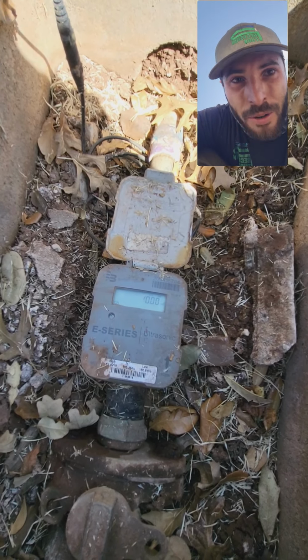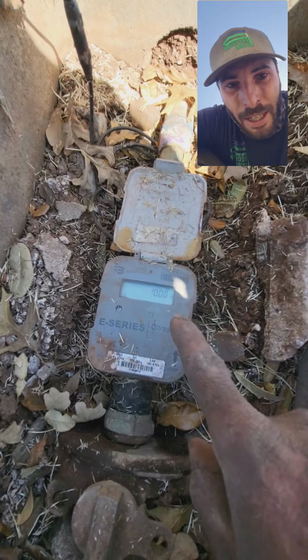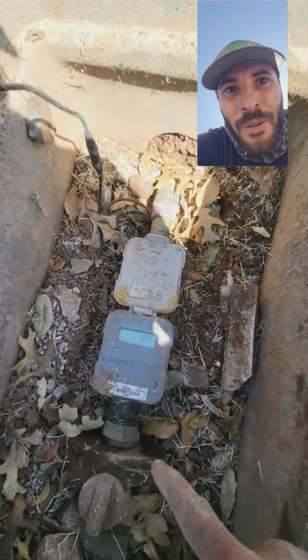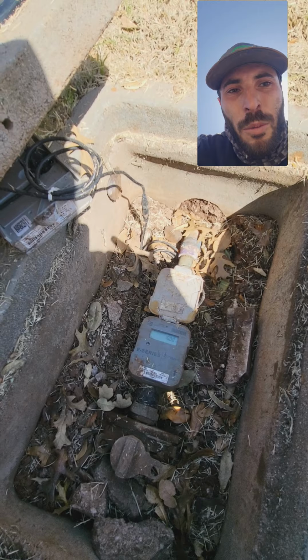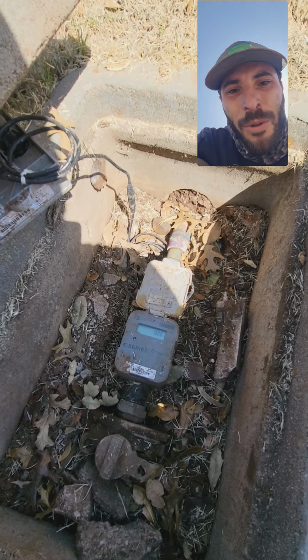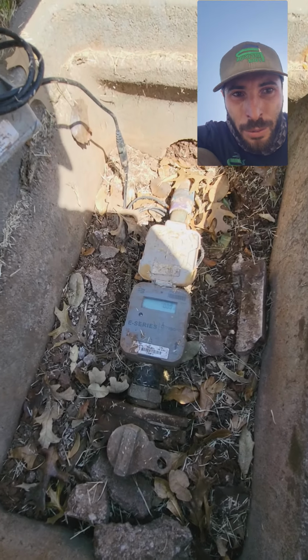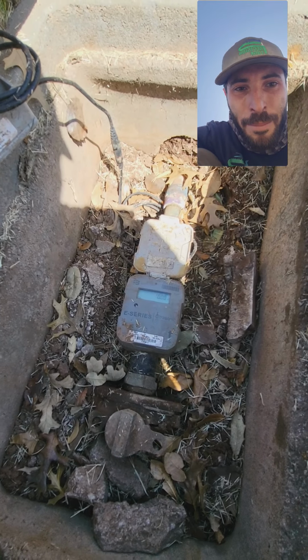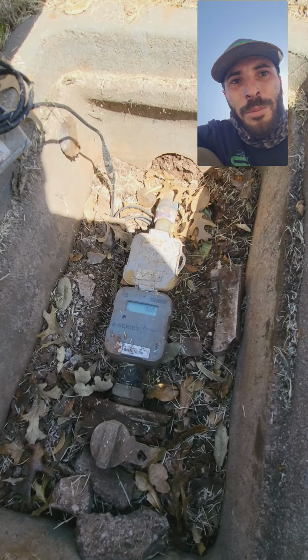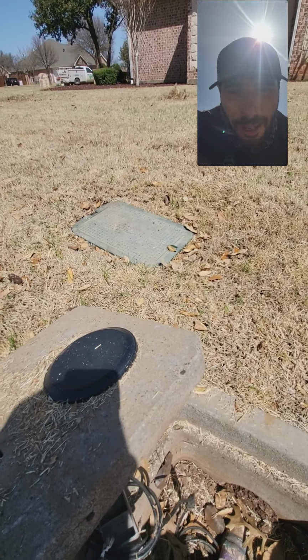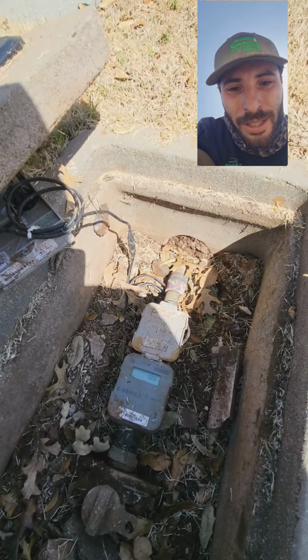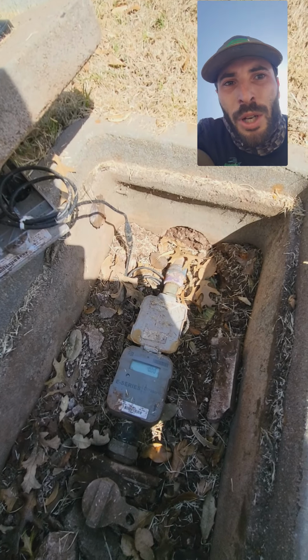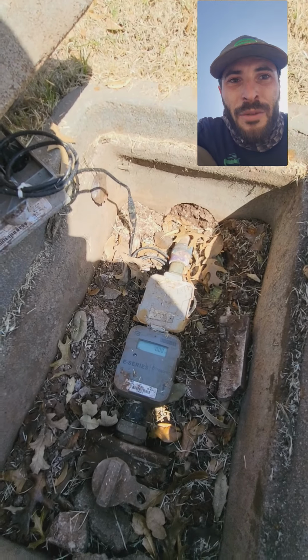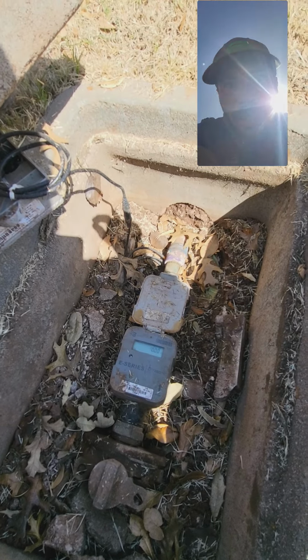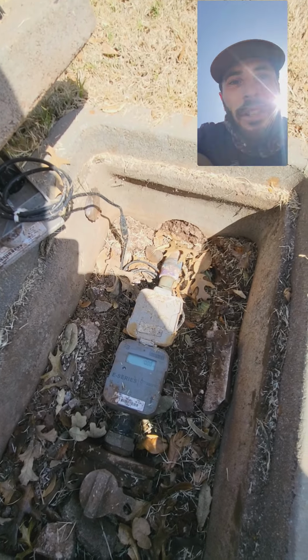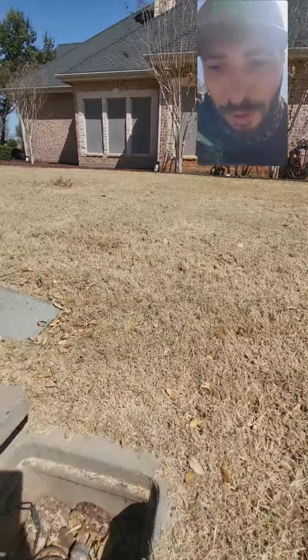If you have a stuck valve or if you've got water moving in any way, it will show a reading here. So whenever you have finished rebuilding a valve or you've done any work on a system, it is always important before you leave, check the water meter, check the water rate. If the water rate is showing a number, turn the isolation valve off for the sprinkler system or one of the check valves on the backflow prevention device. That way you're isolating the sprinkler system. If the water drops to zero, you know that the issue is coming from the sprinkler system. If the water remains high or it remains at a number larger than zero, then you know that the issue is coming from the house and not from the sprinkler system.